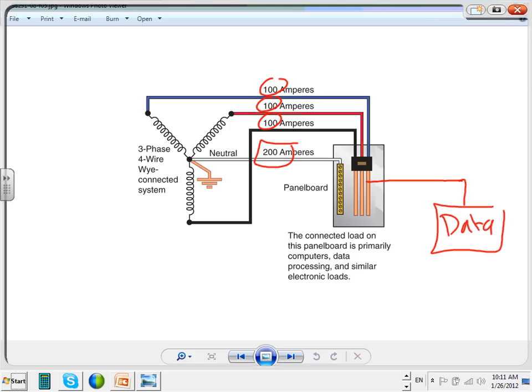Now if you size this one for 100 amp, suppose the conductors were, let's just use the rule, that would be number 1, right? Chris, at 100 amp, I want to size that conductor. That will be number 1. Suppose I size this one number 1, and I size this number 1. Now what's going to happen when you put 200 amp in your number 1 conductor?